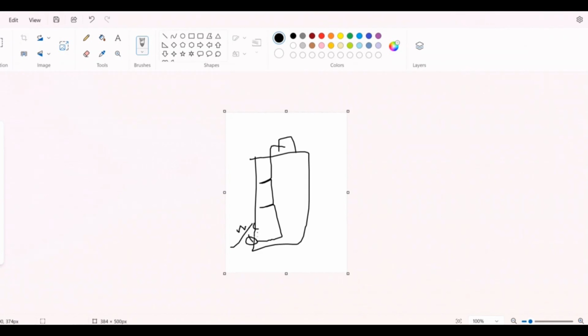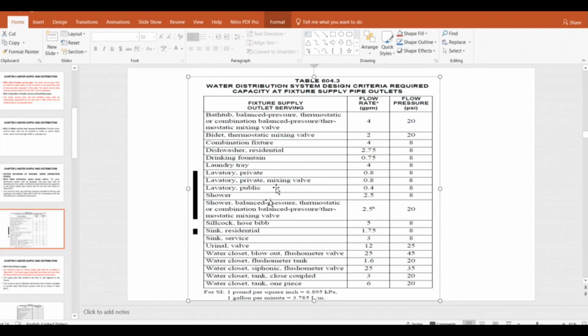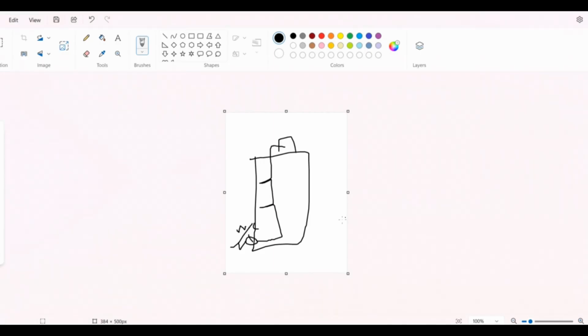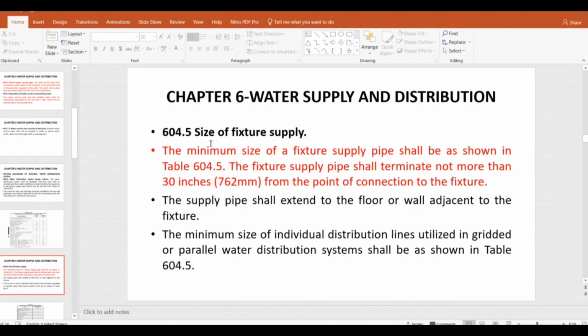Similarly, if you have the lavatory, lavatory means wash basin, you see here the private and public; they have given the minimum pressure as 8 psi. Similarly, if you have the bidet, then 20 psi. If you have the shower, 20 psi. So this is the minimum pressure requirement you have to consider when you go for the pump head calculation. For example, the lavatory needs 8 psi minimum. So we need to consider this minimum requirement for the pump head calculation to size the pump, for all the fixtures.